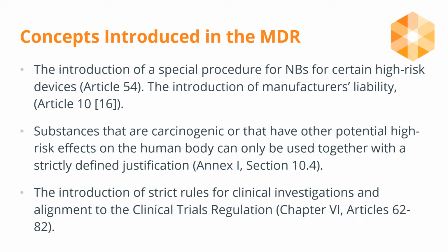Some new concepts have been introduced in the MDR. The introduction of strict rules for clinical investigations and alignment to the clinical trials regulation. Carcinogenic substances, which have a high risk on the human body, can only be used together with a strictly defined justification. And there's also been a new special procedure introduced for notified bodies for certain high-risk devices. Also, the introduction of manufacturer's liability.